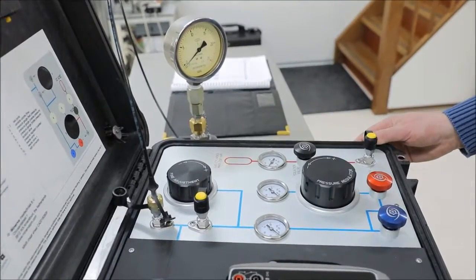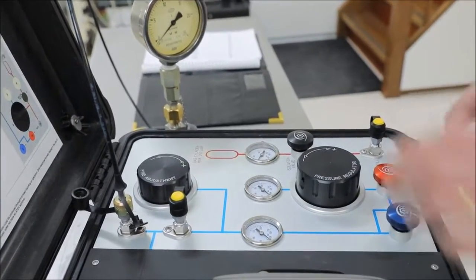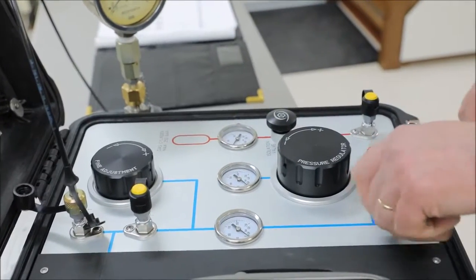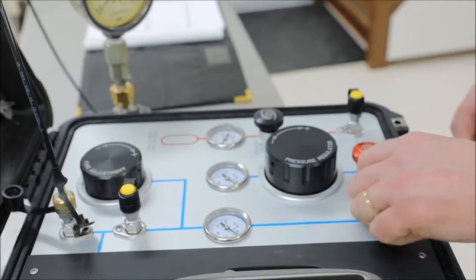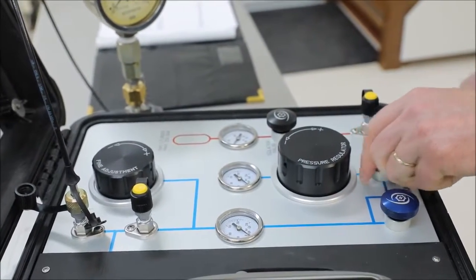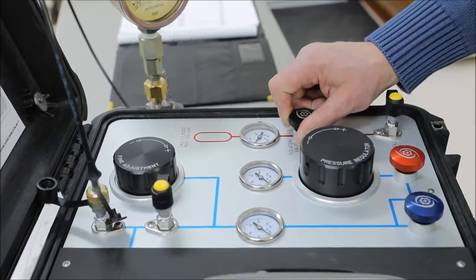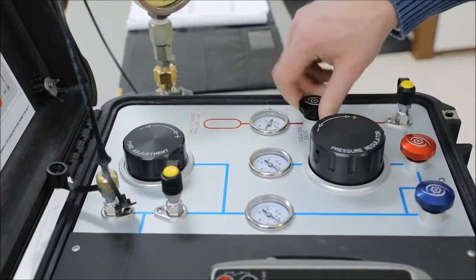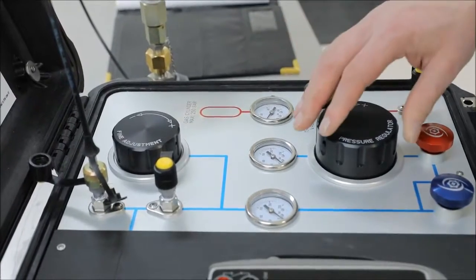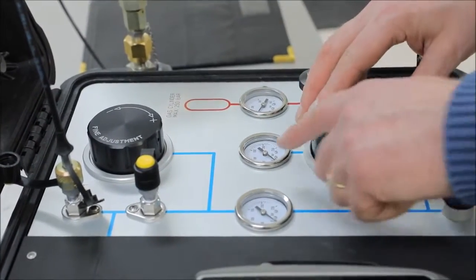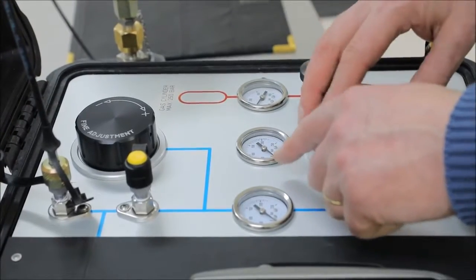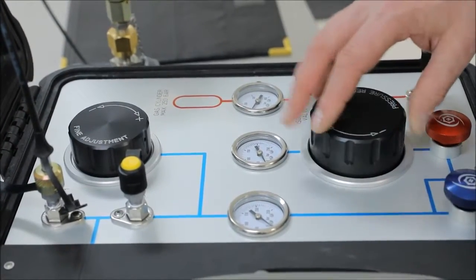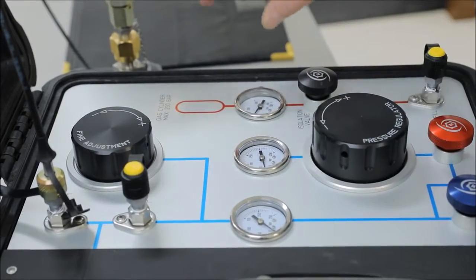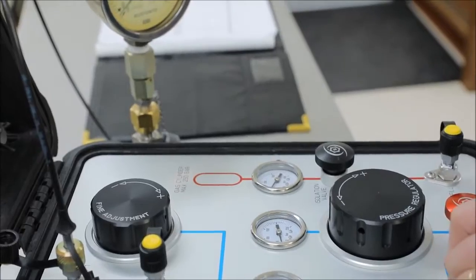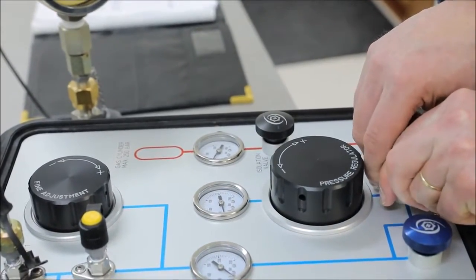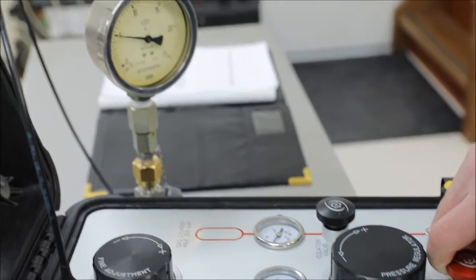Starting from vent conditions, we need to manipulate a couple of valves. First, I'm going to close the vent valve. Secondly, I'll make sure the up valve is closed and I carefully open my isolation valve. Next, I'm going to manipulate my pressure regulator until my regulated pressure indicates a pressure slightly higher than what we are going to perform, so slightly higher than 25 bars. Once that is set, carefully open the up valve and watch my device under test.